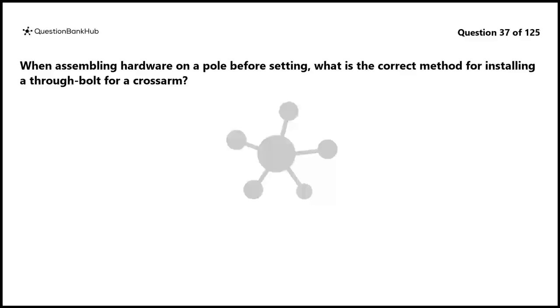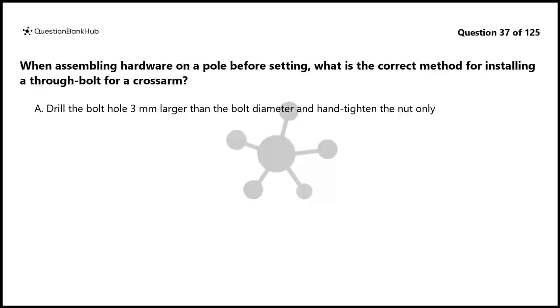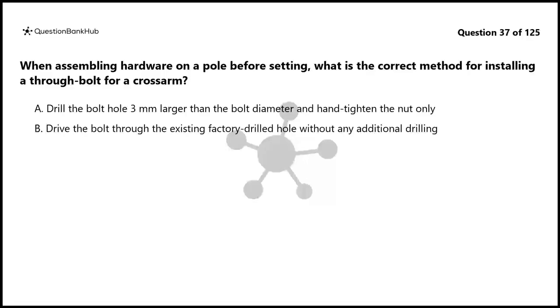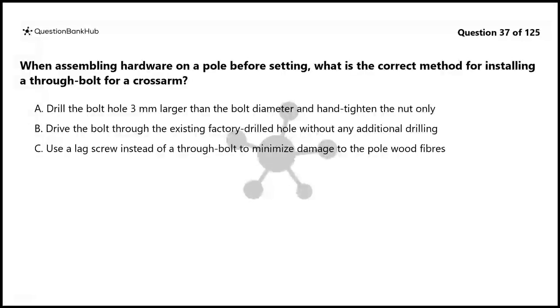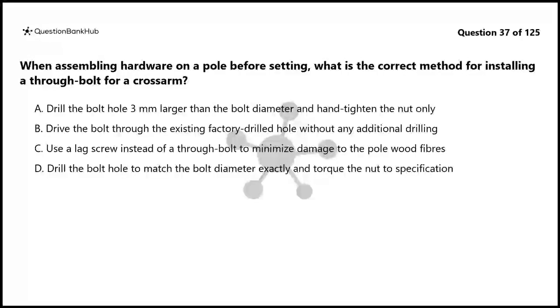Question 37. When assembling hardware on a pole before setting, what is the correct method for installing a through bolt for a crossarm? A. Drill the bolt hole 3 mm larger than the bolt diameter and hand tighten the nut only. B. Drive the bolt through the existing factory drilled hole without any additional drilling. C. Use a lag screw instead of a through bolt to minimize damage to the pole wood fibers. D. Drill the bolt hole to match the bolt diameter exactly and torque the nut to specification.